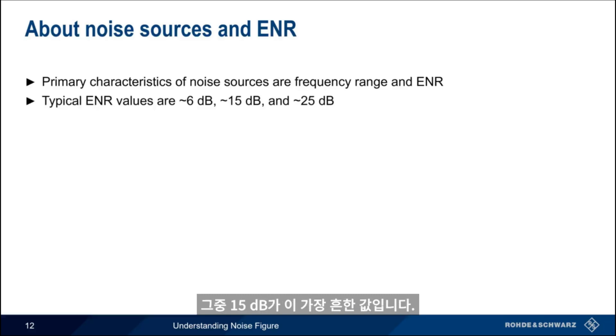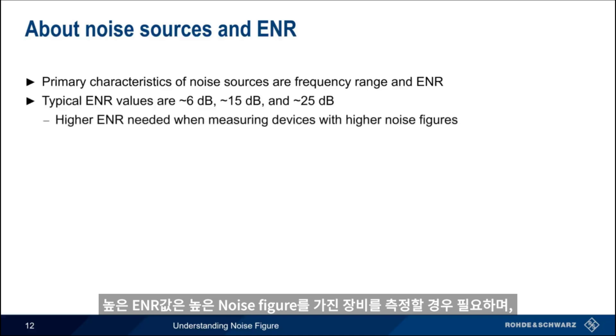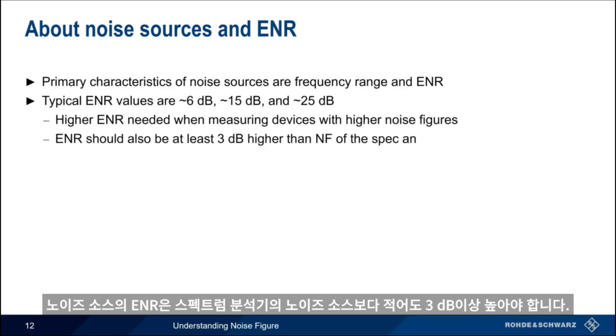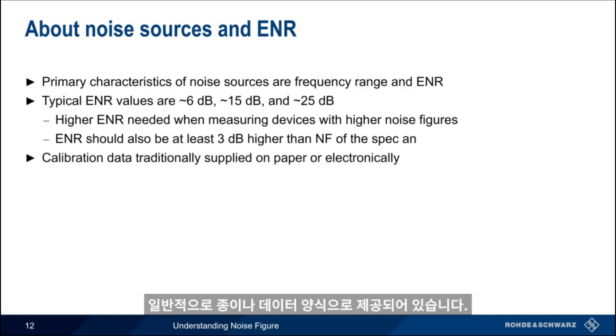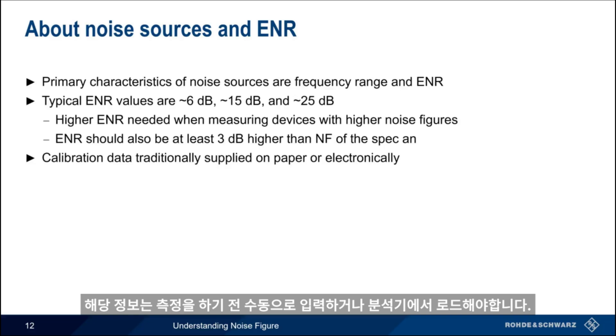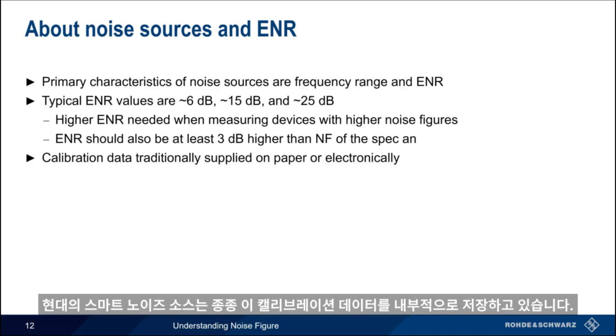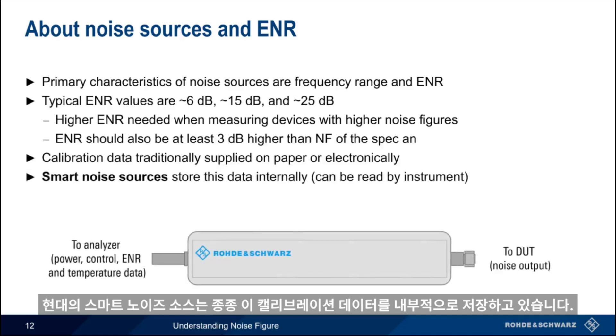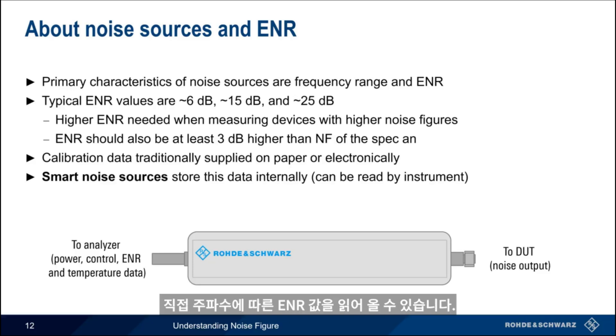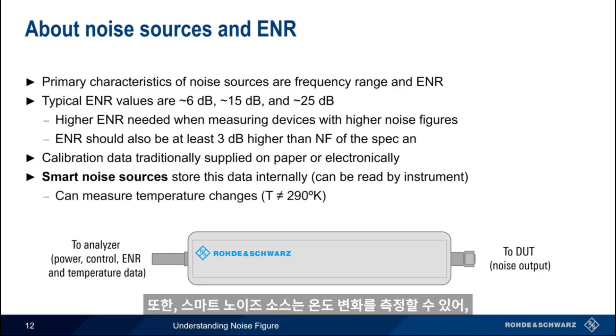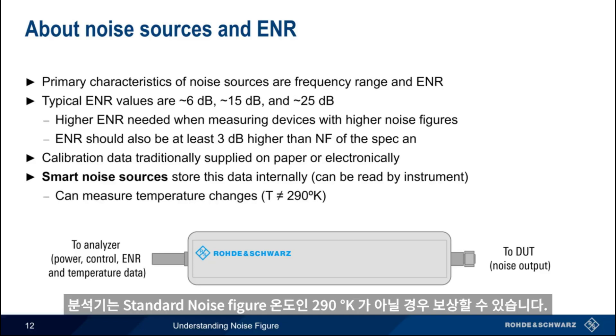Higher ENR values are needed when measuring devices that have higher noise figures, and the source's ENR should also be at least 3 dB higher than the noise figure of the spectrum analyzer. The ENR versus frequency values of a noise source are referred to as calibration data, which traditionally was provided in either paper or electronic format and would have to be manually entered or loaded into the analyzer. Modern smart noise sources often store this calibration data internally — within the source itself — and the analyzer can then read the ENR versus frequency values directly from the source. Smart noise sources can also measure temperature changes, allowing the analyzer to compensate for measurements not made at the standard noise figure temperature of 290 degrees Kelvin.